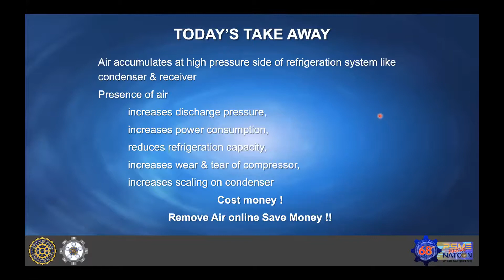Secondly, when there is water in the system, water accumulates on the low pressure side of the system. So there's a difference between air and water. Air accumulates at the high pressure side, and water accumulates on the low pressure side of the system. Ammonia has a great affinity with water. The moment water comes into contact with ammonia, it becomes hydrous ammonia, and hydrous ammonia means there is a change in the operating pressure conditions. You do not get the same temperature at the same rated pressure for ammonia.